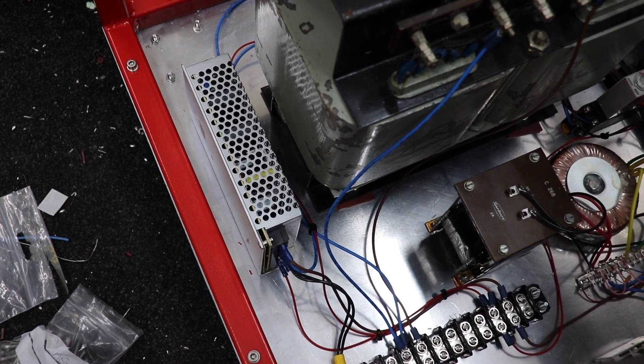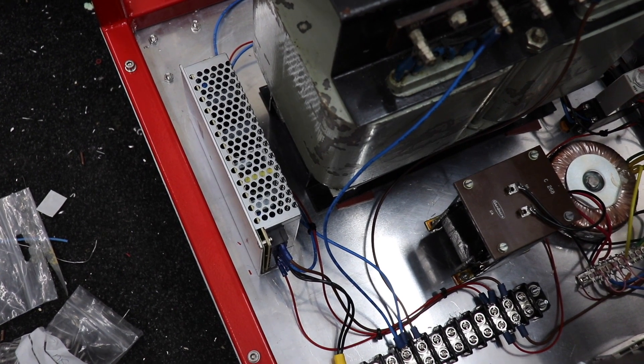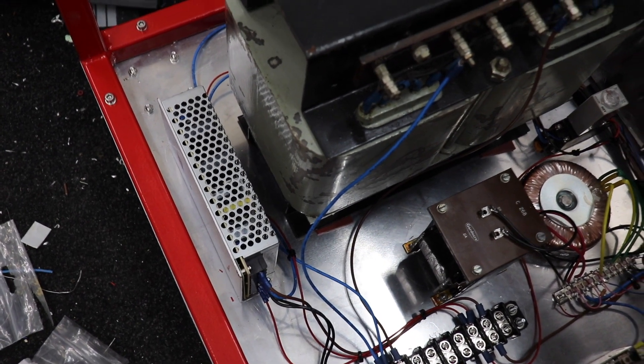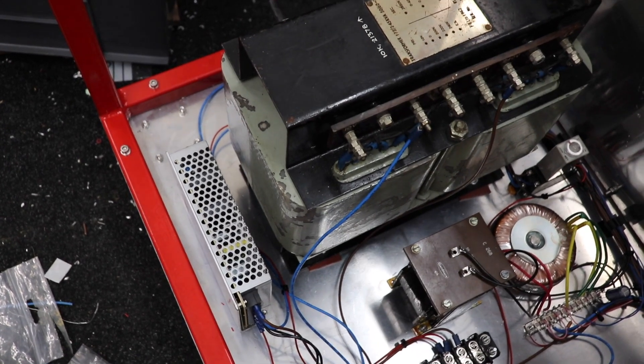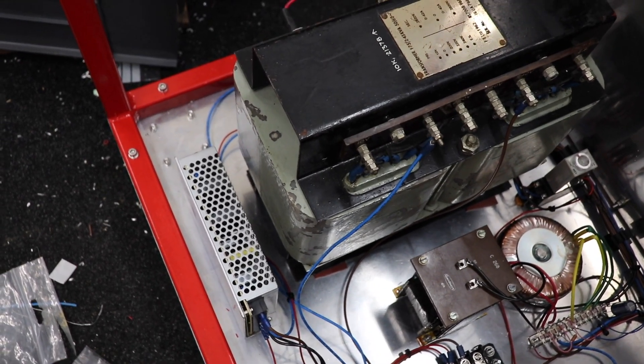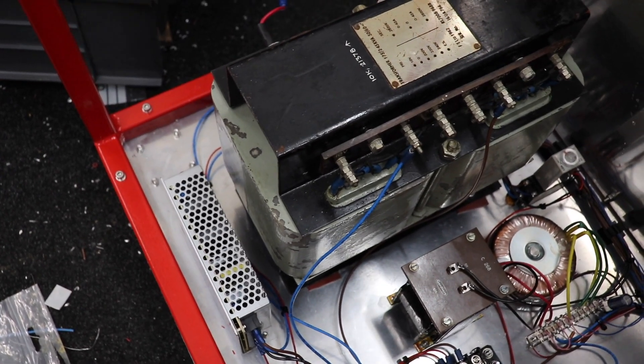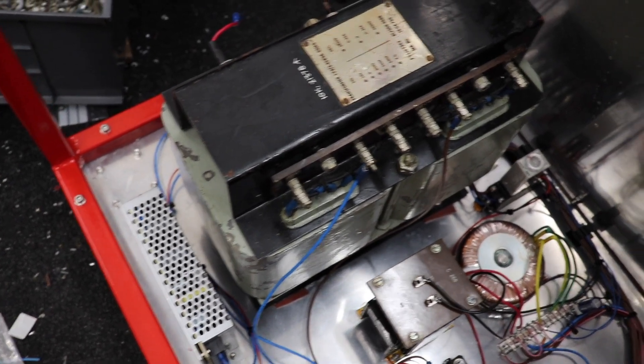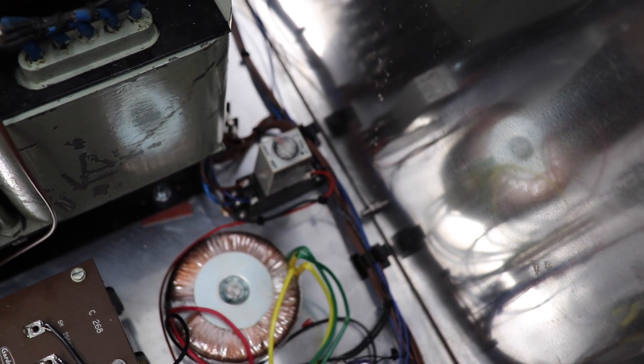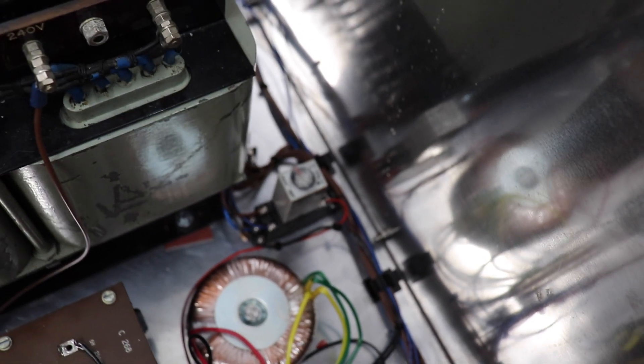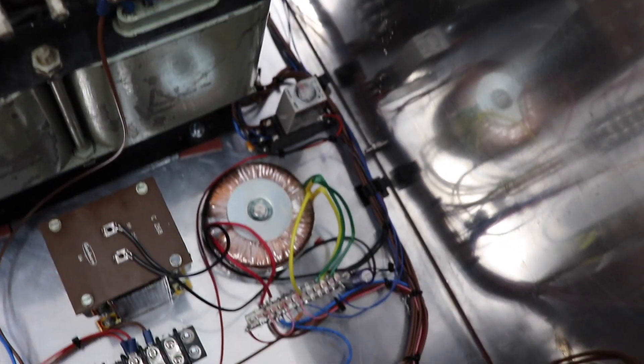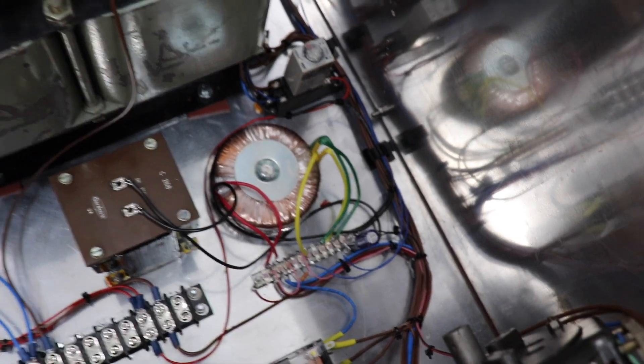The idea of that is that it basically supplies control voltages for the relays and the circuitry protection circuitry in the main electronics unit. Down in the corner we've got a timer relay which is for basically switching on the HT after about 45 seconds because you need to give a bit of time for the 872A mercury vapor rectifiers to warm up before you switch on the HT.